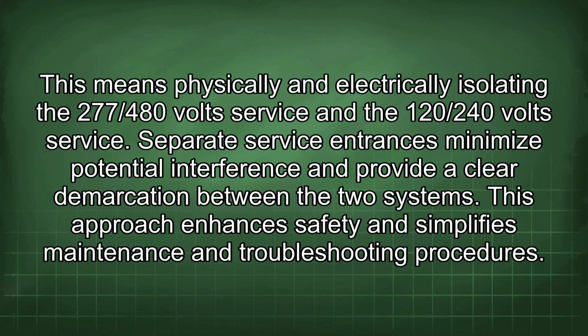This means physically and electrically isolating the 277/480 volt service and the 120/240 volt service. Separate service entrances minimize potential interference and provide a clear demarcation between the two systems. This approach enhances safety and simplifies maintenance and troubleshooting procedures.